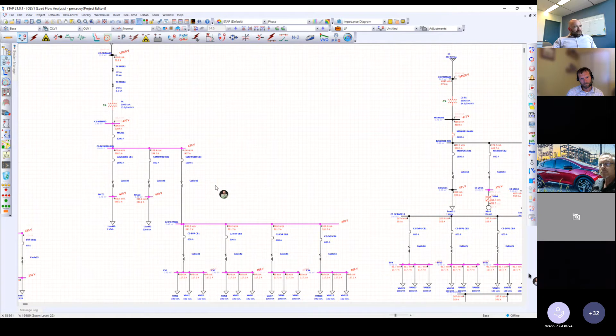But if you look at that service and want to add, say, a dozen charging stations for van fleets, you're adding about 1,600 amps of load at 480 volt. They might be able to handle that on a voltage drop standpoint. Maybe they're only really using those part of the time, so you could take some of these, put half of that out of service, and run the same calc.